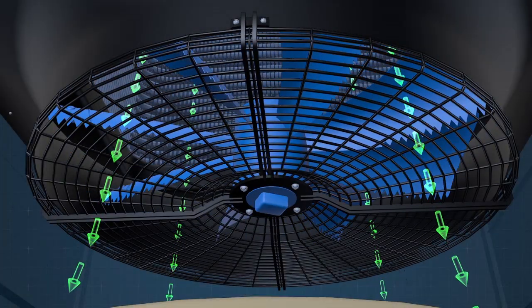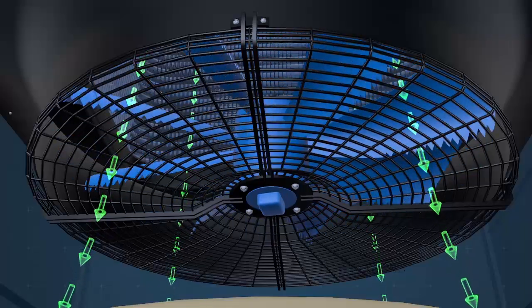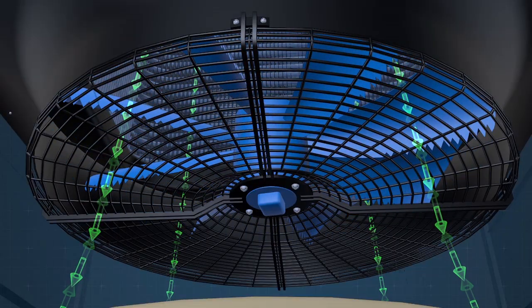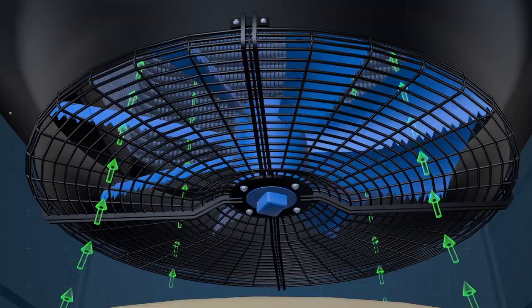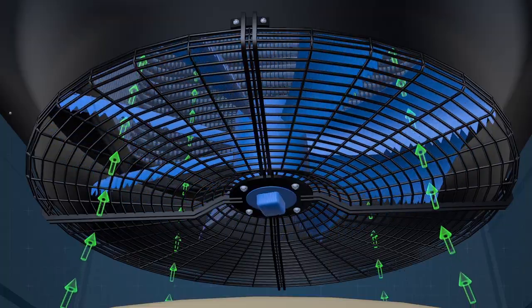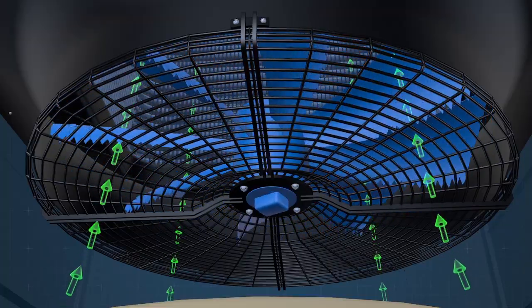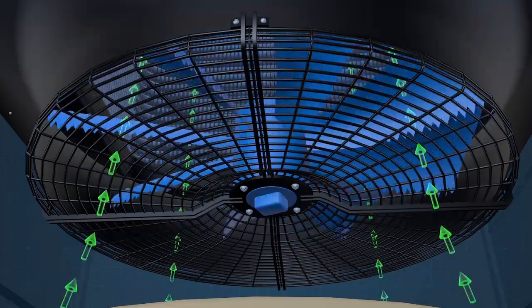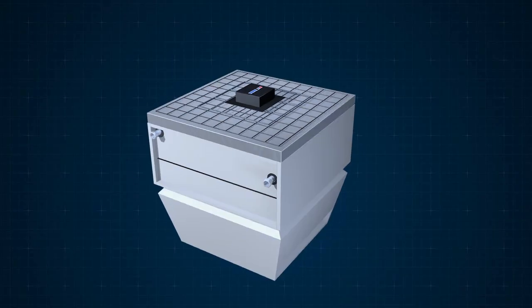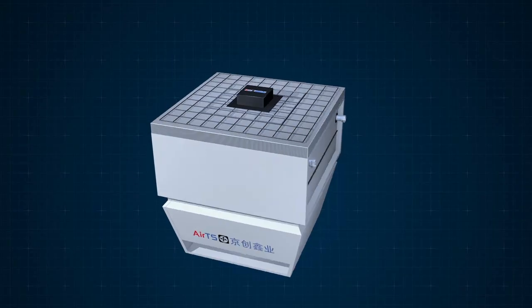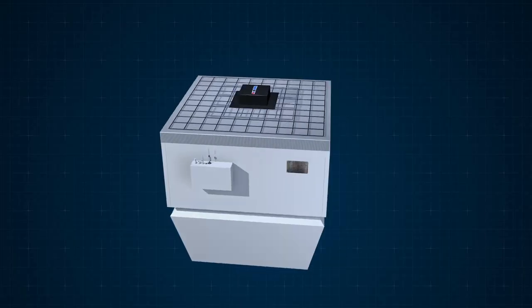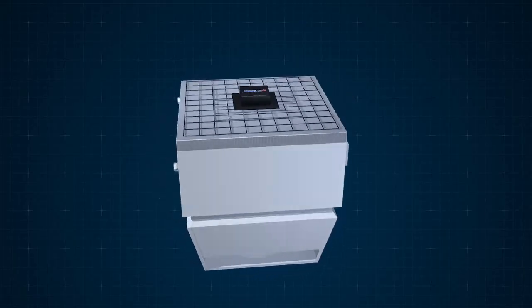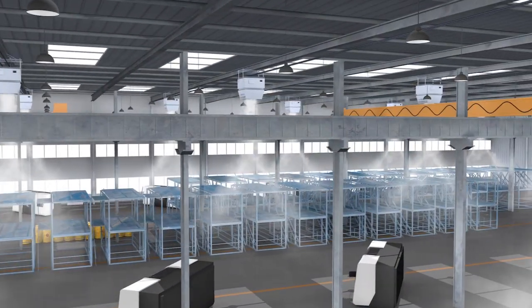When the dedusting command is enabled, the frequency converter controls the fan to rotate reversely, thus changing the filter screen air inlet state to the filter screen reverse blowing state. When reaching the maximum blowing speed, the vibration device is started to separate the dust from the filter screen, thus achieving automatic cleaning and maintenance of the filter screen.